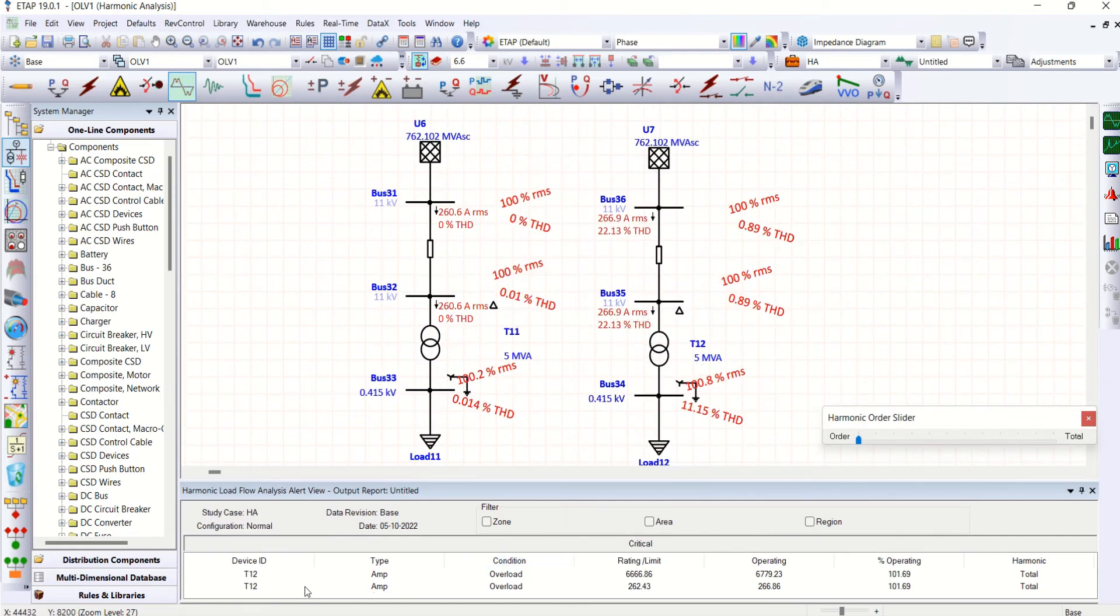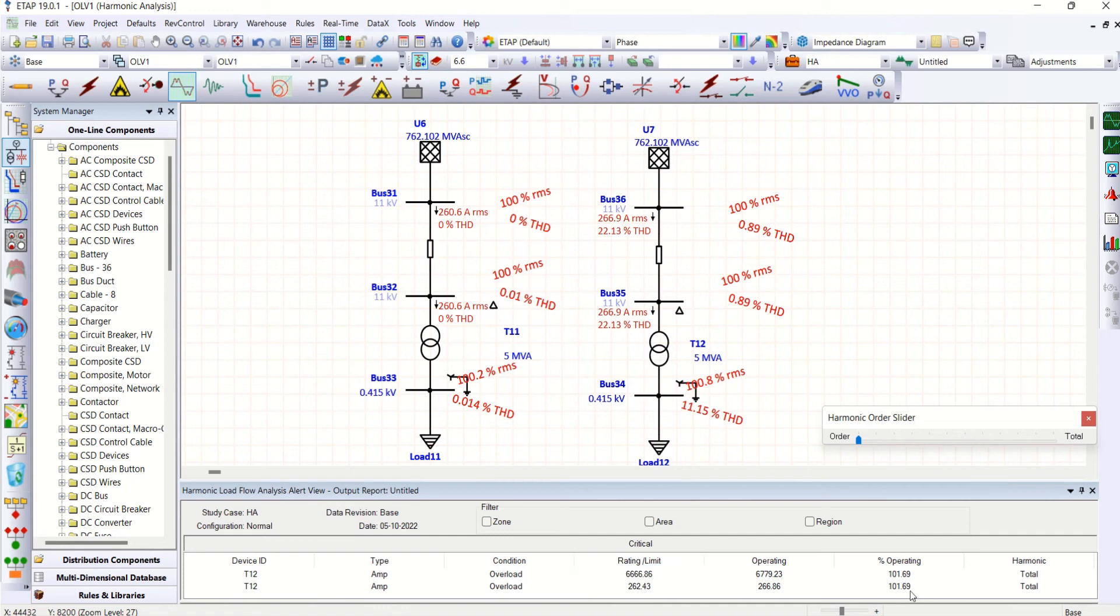The current is increased due to this increase in current. So look at the transformer T12, both in primary as well as secondary side overloaded. Okay, we are overloading the system by 101.69%. So in this scenario, we can use K-rated transformer.